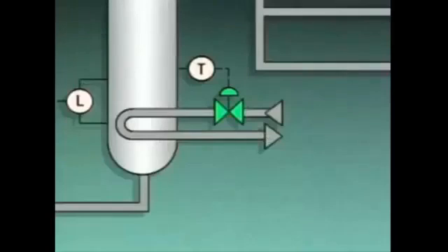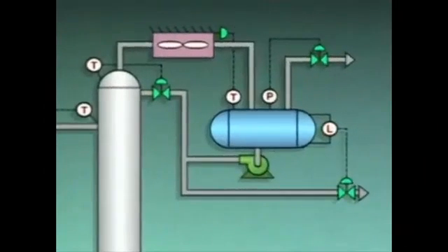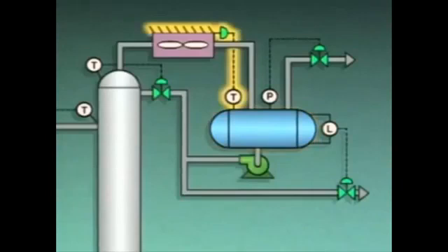The control system's energy balance control loops react to an increase in the bottom temperature to maintain the system's energy balance. An increase in the bottom temperature means that there is a greater amount of vapor flow. As the additional vapor is condensed in the condenser and flows into the receiver, the temperature of the liquid in the receiver increases. The condenser temperature control loop senses the increase in temperature in the receiver. This control loop then adjusts the louvers in the path of the forced air from the fans in the condenser to cool the increased amount of vapors.